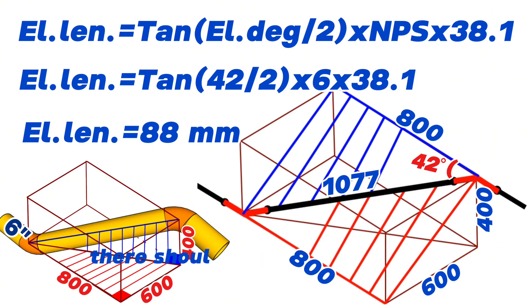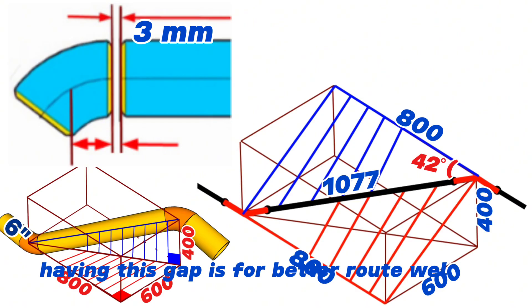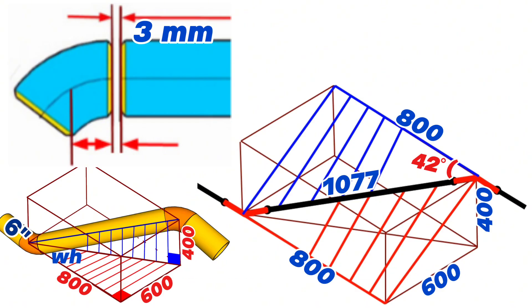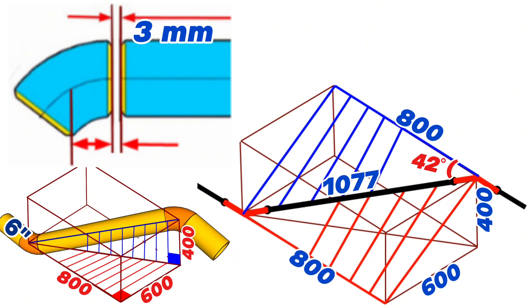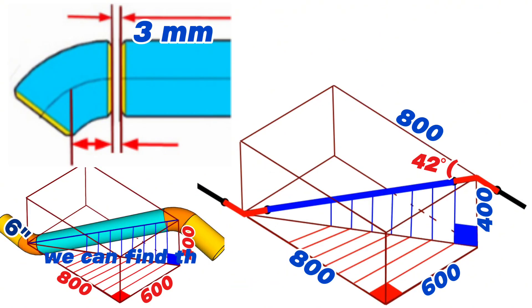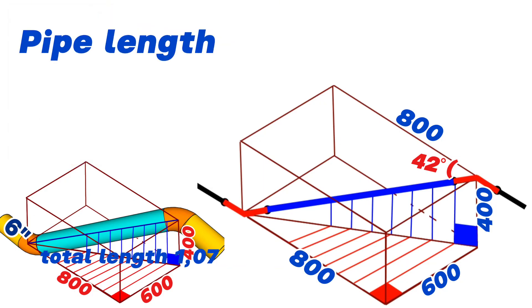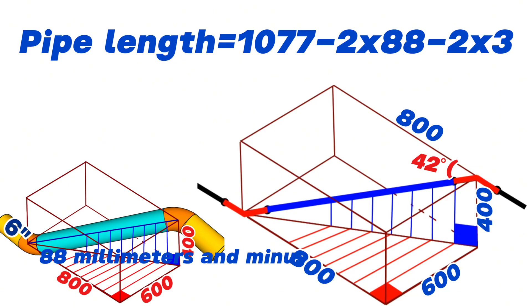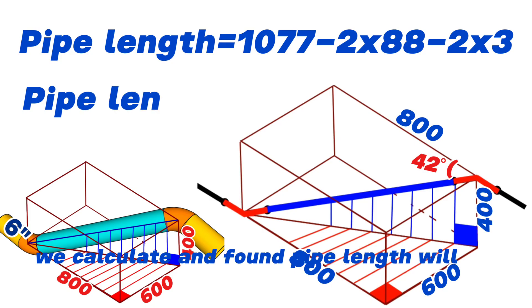During fit-up there should be a gap of about 3mm between the pipe and elbow to be welded, for better root welding. We take these gaps into account when calculating the length of the blue pipe section. Pipe length equals the total length of 1077mm, minus 2 times the 42-degree cut elbow dimension of 88mm, minus 2 times the welding gap of 3mm. The calculated pipe length equals 895mm. So the blue pipe section length is 895mm.